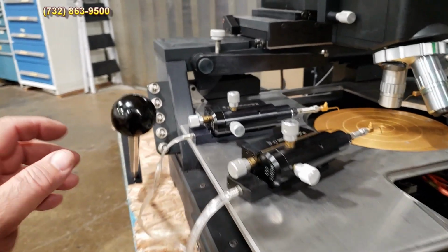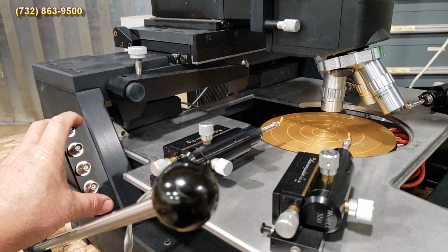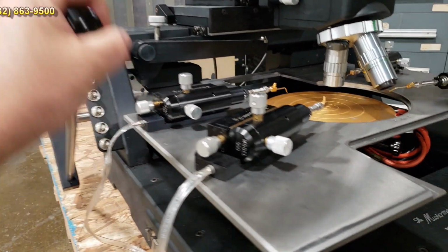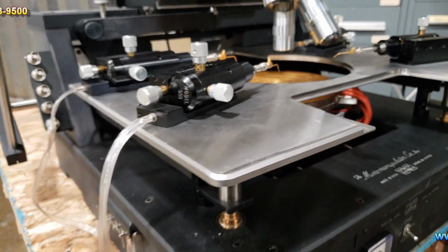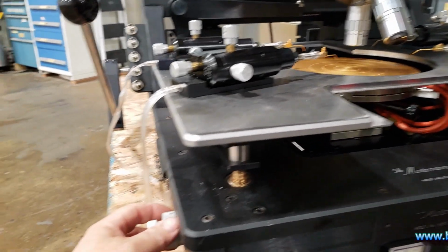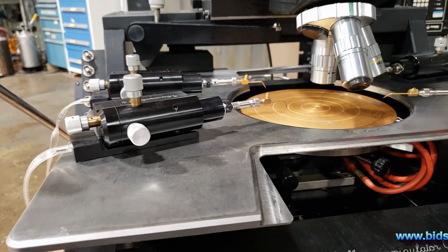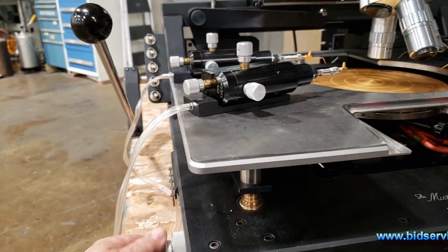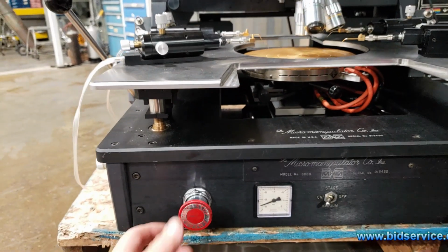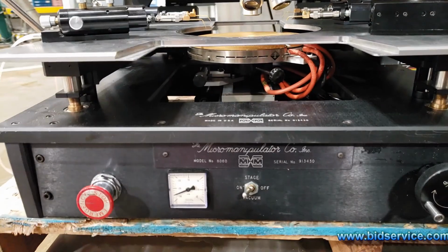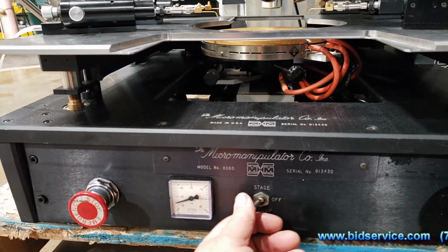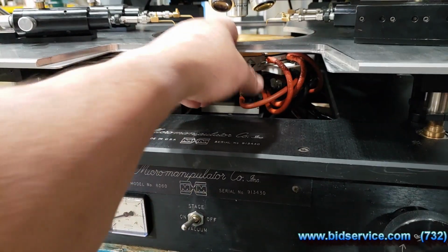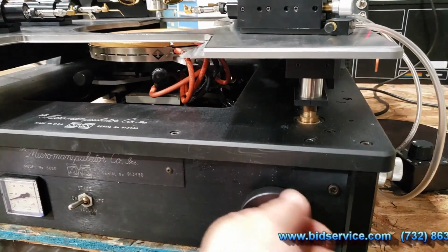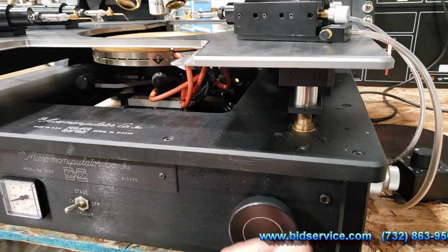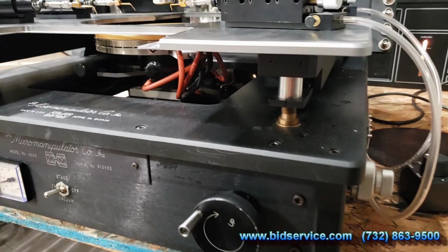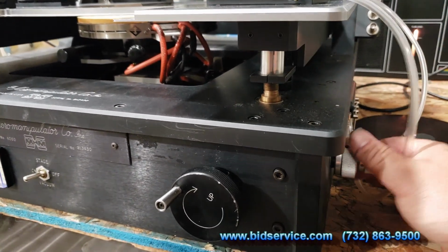For your controls over here, you have your connections for your probers. You have your platen lift, and it removes the microscope out of the way. Then right here is your knob for your X control on the chuck. There's also a fine on here. The EMO is connected to a connector in the back. You have your vacuum gauge. This is also the vacuum for your chuck. You have your platen micro adjust to be able to finely tune the platen to go down to the chuck. And over here you have your Y adjustments. Here's your coarse and then your fine.